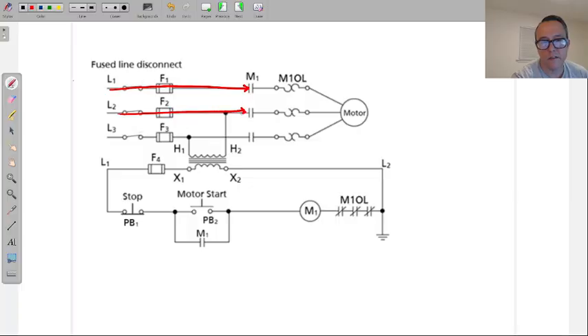All three of those phases were good. There, voltage is there, voltage going into the transformer, again assuming the transformer is fine. Voltage, and we're going to ignore here because it's not really voltage, but hot. Stop button, normally closed, voltage goes through. Start button, normally open, voltage pauses. Connected to this same line, voltage going down, normally open contact, voltage stops. So right now, here is where voltage is and where voltage isn't.